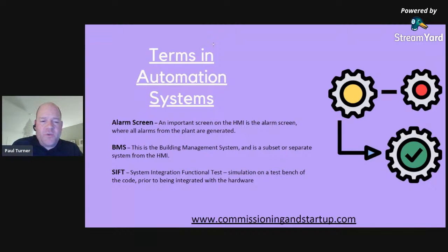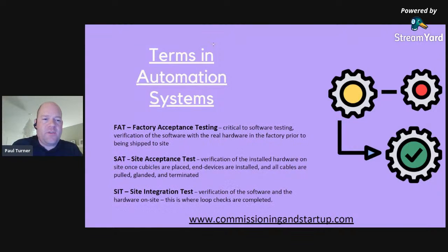So with regards to getting ready for some of the commissioning tests, some terms you might hear is a SIFT, a system integration functional test. Now this is the simulation aspects that are completed on a test bench prior to getting to testing in the field. Factory acceptance test, and we'll go through this one a bit more in a few slides, is very important to the commissioning phase. The factory acceptance test, and it really should be an integrated factory acceptance test, is confirming that the hardware and the software function correctly before any of the systems even arrive at site.